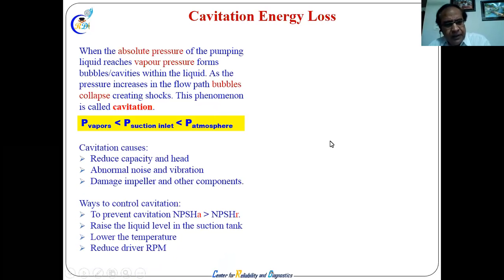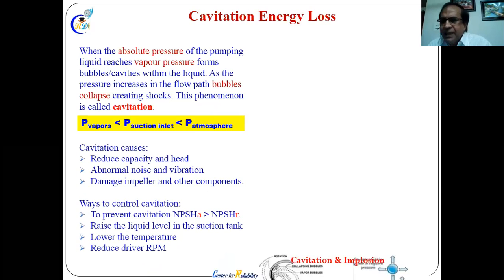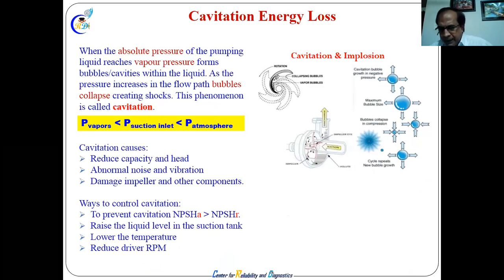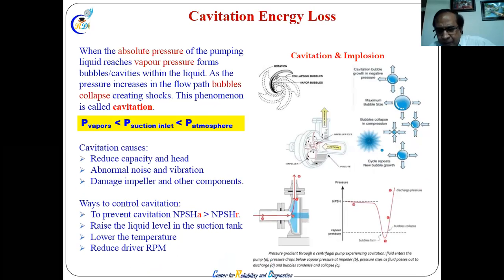That is the thing. And these are the causes. It can damage the entire pump internals, the blades, everything, and the available head should always be higher than the required. So whatever is required at the pump inlet must be available from the atmosphere, and it should not go down to the vapor pressure. If it reaches vapor pressure, then bubbles will form. And if there is a bubble, then it implodes. That bubble will break. That is called implosion.